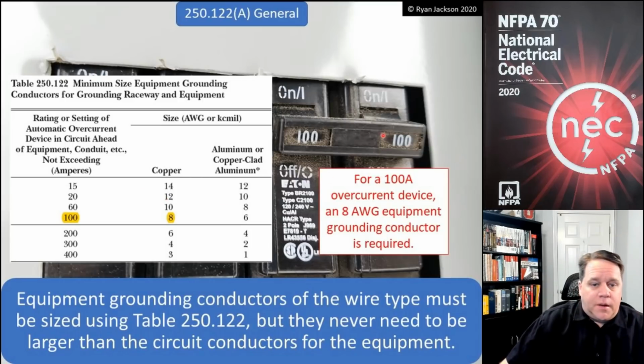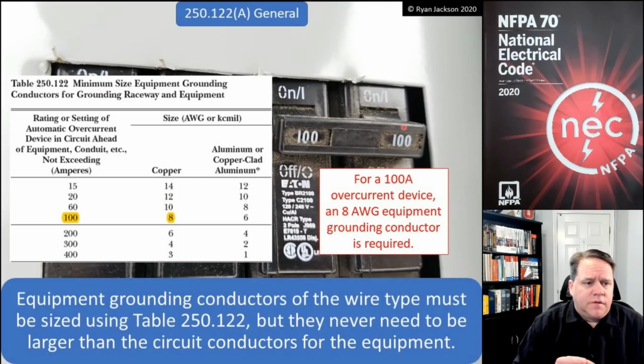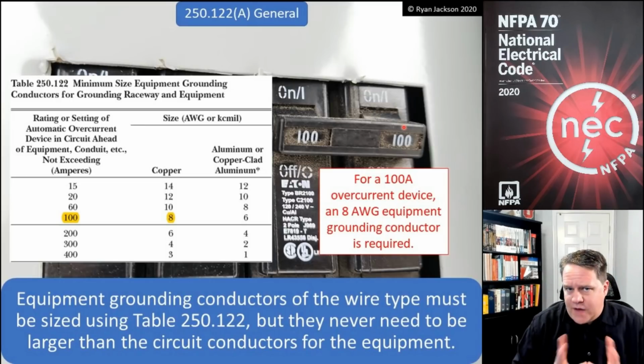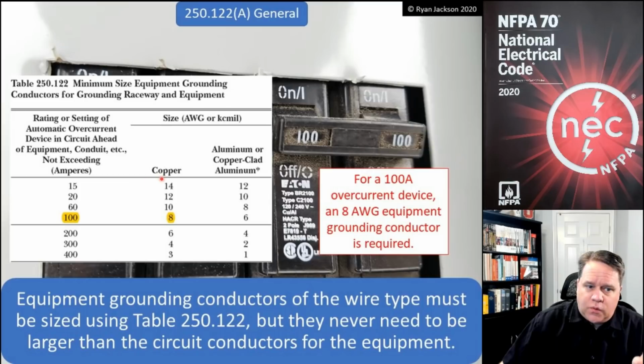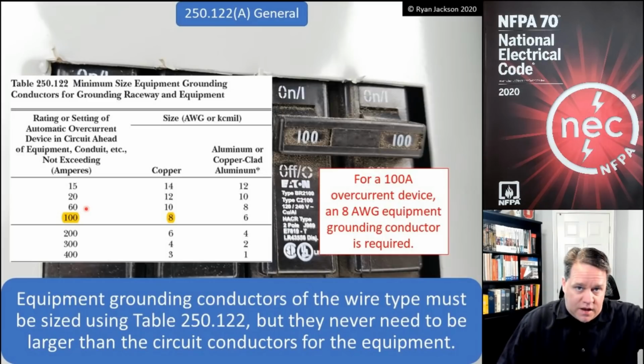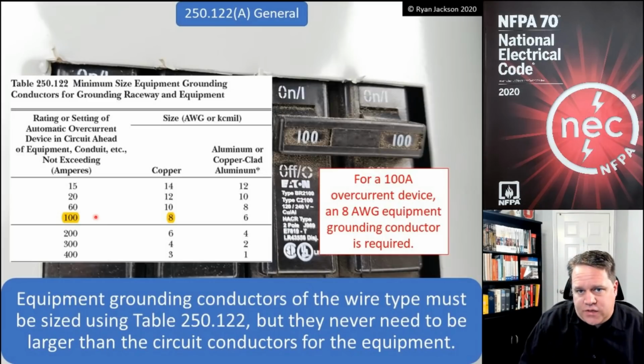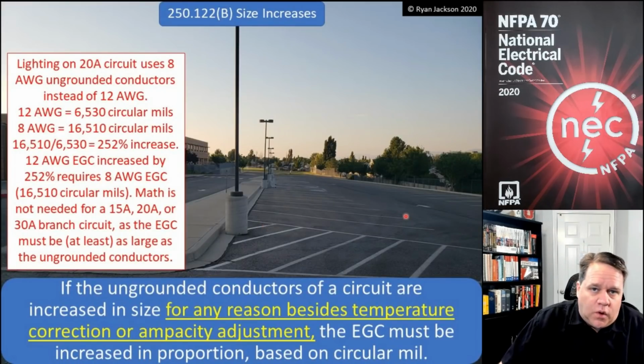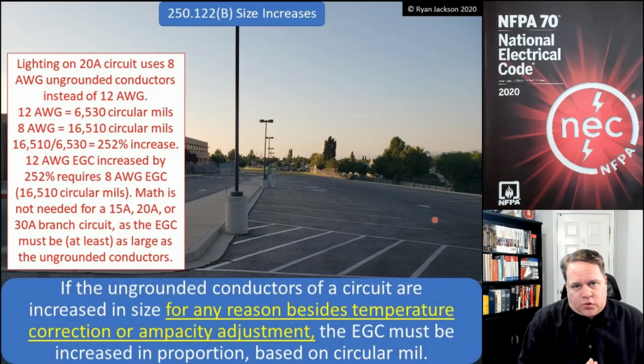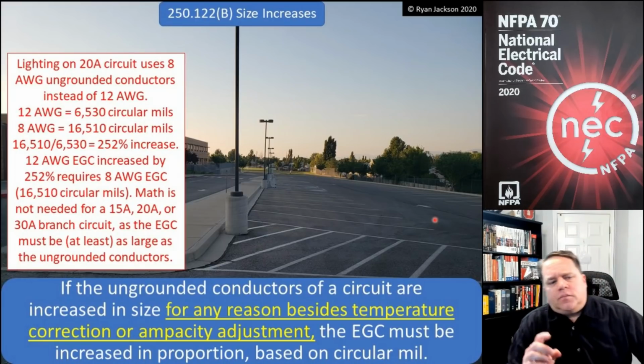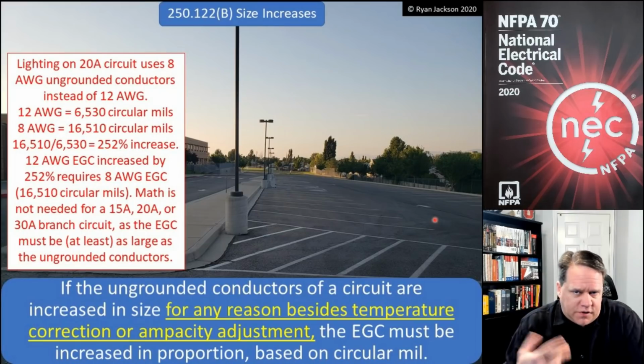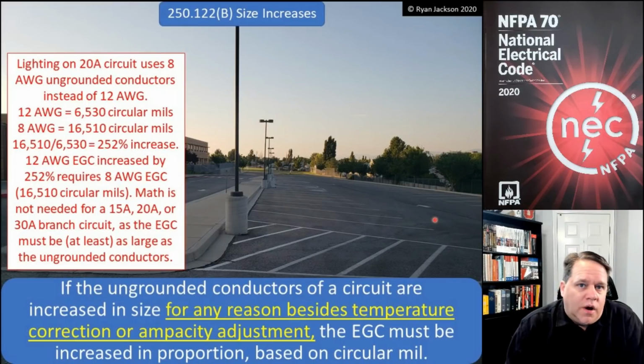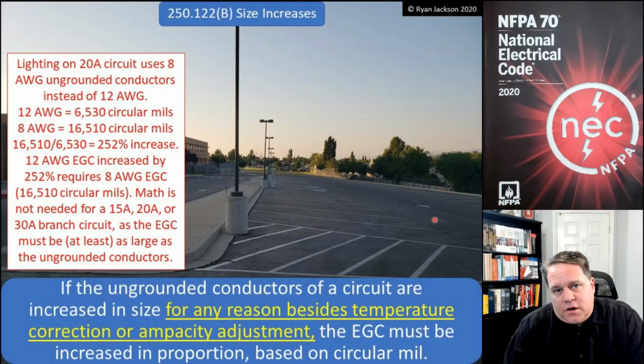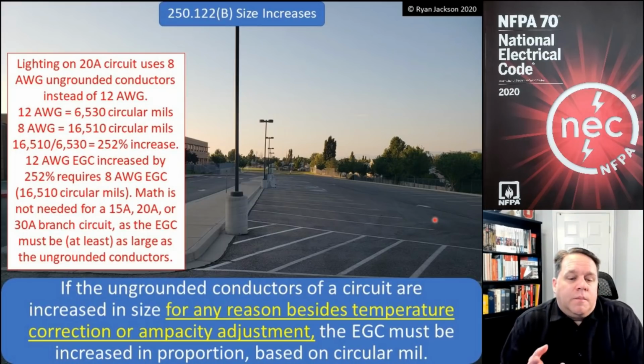So we're going to do a little bit of math here in a minute, but I want to point out that for 15, 20, or 30 amp circuits, the math is going to be extremely easy. Just remember that the green wire has to be the same size as the black wire. Once we get to 35 amp circuits and greater, then we're going to have to do a little bit of math when it comes to section 250.122(B). What this rule says, and you can see that it was revised in the 2020, is if the ungrounded conductors of a circuit, the hot conductors, are increased in size for any reason other than temperature correction or ampacity adjustment, then the equipment grounding conductor must be increased in proportion based on circular mil.